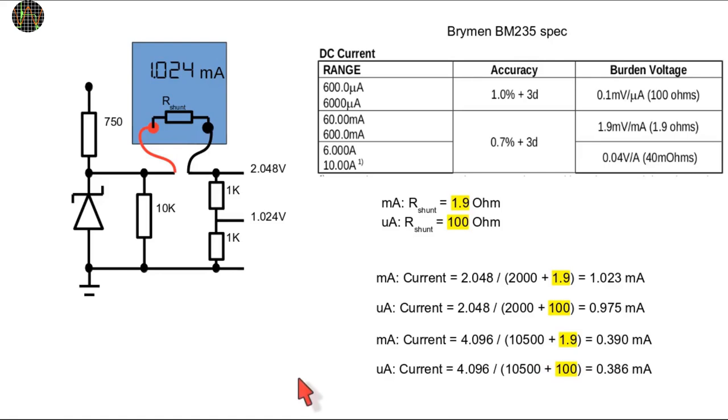To be clear, there is nothing wrong here. The multimeter and the references work just fine and within specs. It is simply something you need to be aware of and take into account when measuring. So this multimeter in the microamp range should always read 975 microamps. If it reads significantly more or less current, something is wrong.